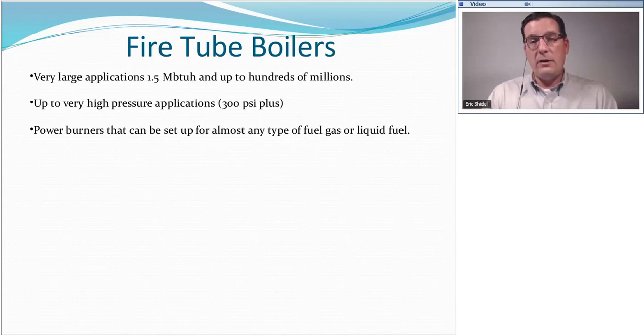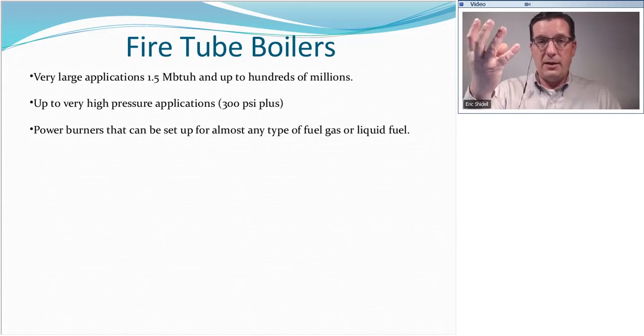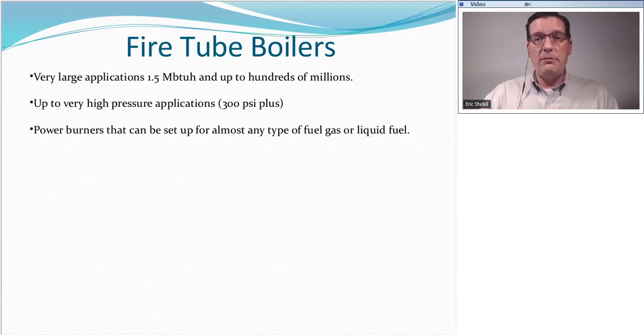Now, in the event that we were to just casually open a valve to take a water sample, as soon as that 300 plus degree water hits the atmosphere, it's going to be an explosion of energy. That water is going to immediately burst into steam, and it's going to fill the entire room and literally boil everything alive in that room. It can be very dangerous.